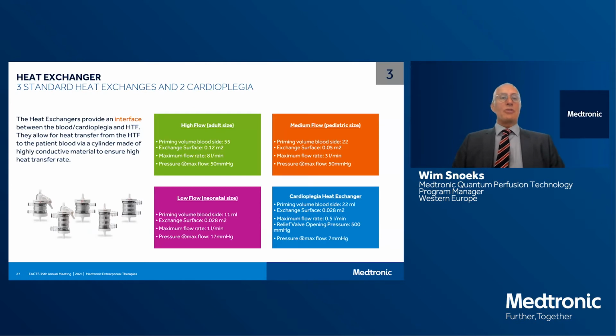So the disposables: there are 3 standard heat exchangers for the arterial loop, as we discussed, and 2 for the cardioplegia. The 3 standard heat exchangers are the high flow, the medium flow, and the low flow. The high flow is for adult use, the medium flow is for small adults and pediatric use, and the low flow is for neonatal circuits. For the cardioplegia system, we have 2 sizes, one for the adult system and one for the pediatric and neonatal side.